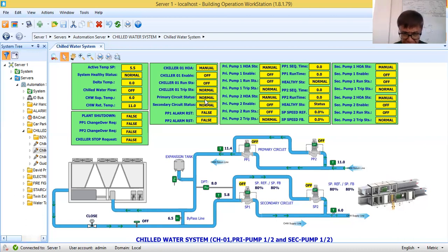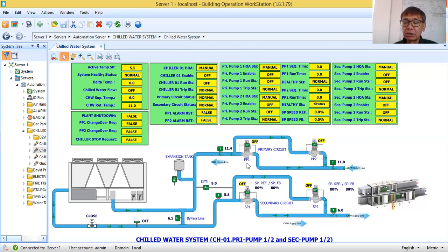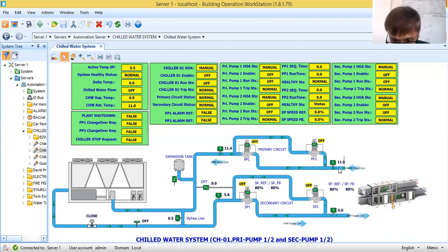We also monitor primary circuit status and secondary circuit status to know if one or two pumps are running. The sequence of operation is: one primary pump will run and one secondary pump will run for the system. There is no chance that both pumps will run simultaneously because the design is duty and standby — primary pump duty and standby, secondary pump duty and standby.